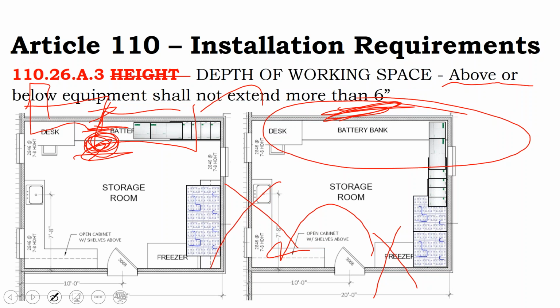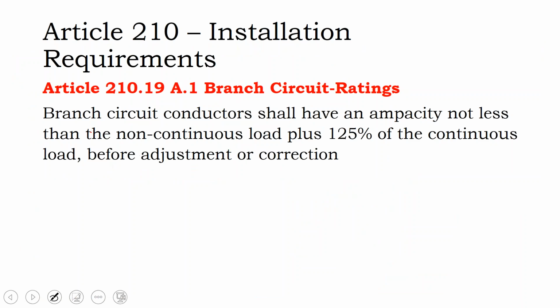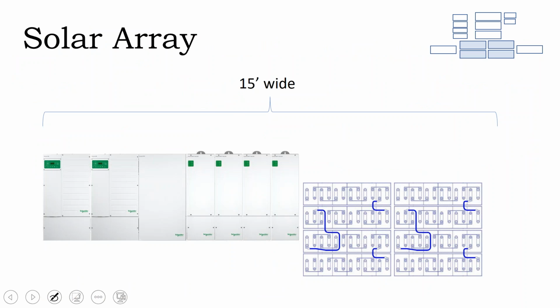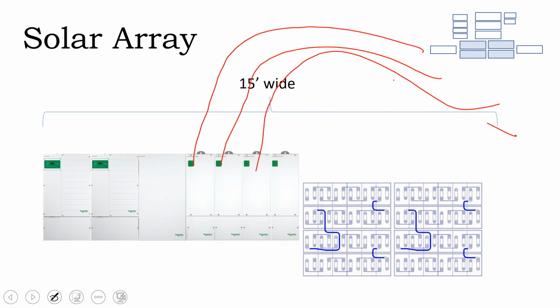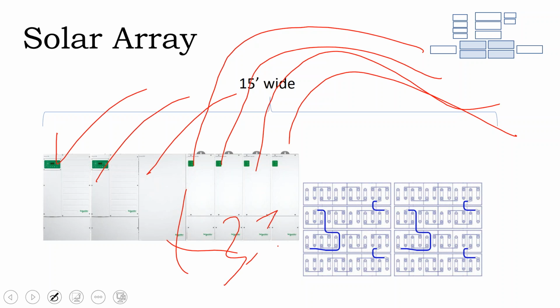Now we have a 30-inch solar inverter, a 30-inch battery inverter, a 30-inch service panel, and then for our system, we also have these charge controllers coming in from the solar array itself, and these could be located somewhere else. They don't have to be located right there. And so what we're looking at as a minimum size to our inverter wall is about 3, 6, 9 plus 3.5 plus 3.5, 7 plus 8. Now we're looking at a 25-foot inverter wall to be code compliant.